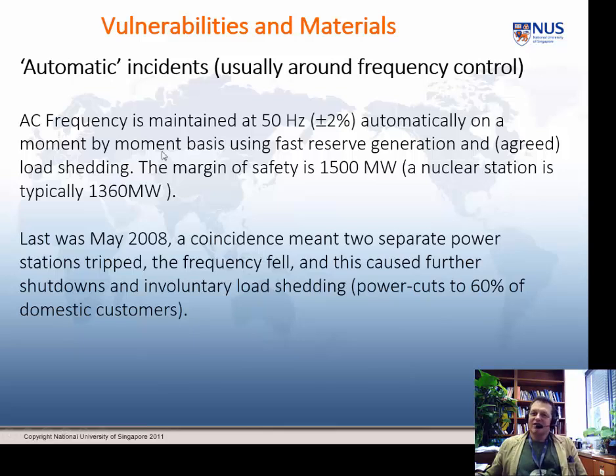To give you an idea, and we're talking about the UK situation here, the margin of safety is about 1500 megawatts, and to give you a comparison, a medium-sized nuclear power station is about 1360 megawatts. So effectively, it's about a decent-sized power station. Now, this is a UK incident, and the last major automatic accident was in 2008 in the UK in May. And as often happens with accidents, a coincidence occurred. Two separate power stations, for different reasons, tripped out. That is, a condition occurred within the power station which meant it stopped pushing power into the grid for a local reason. They tripped out within maybe a minute of each other, pure blind coincidence.